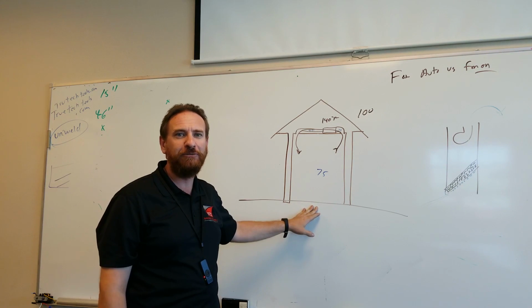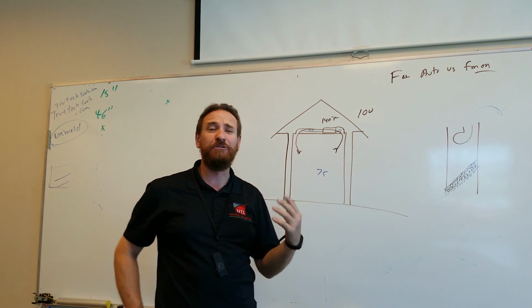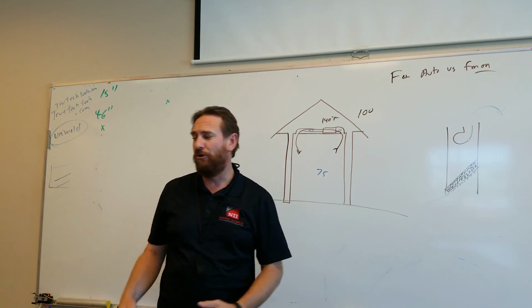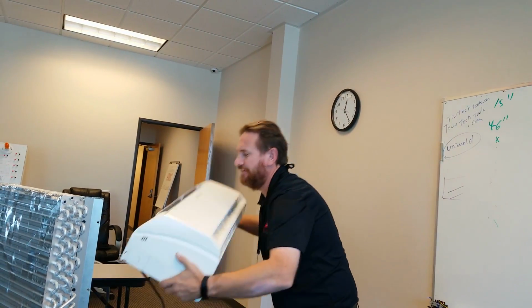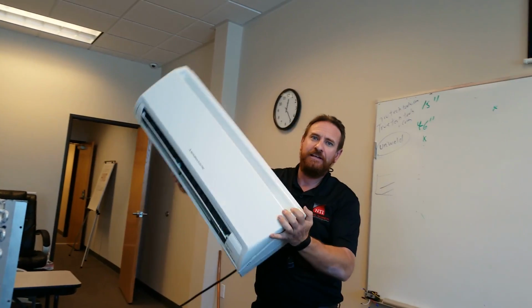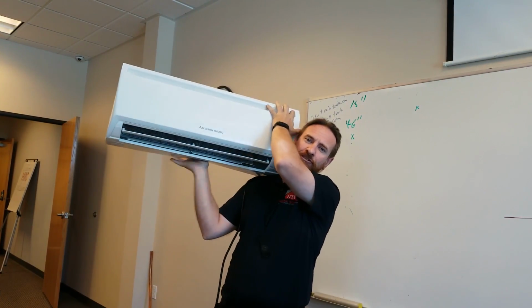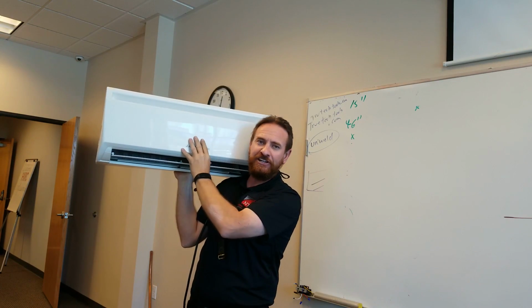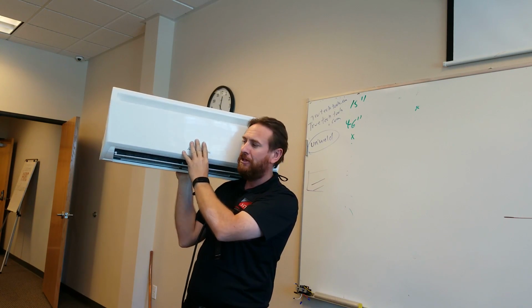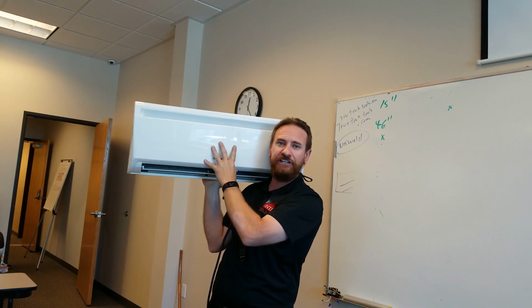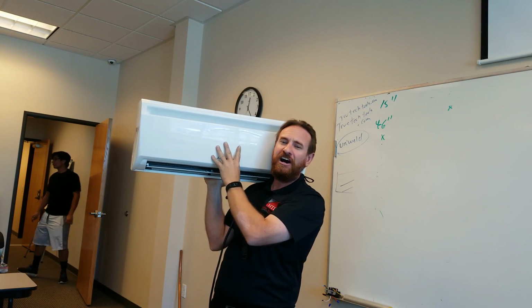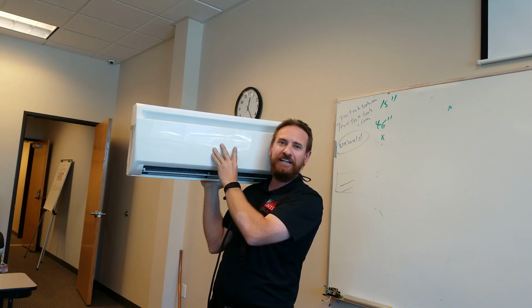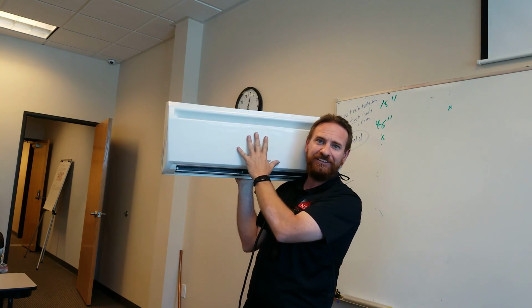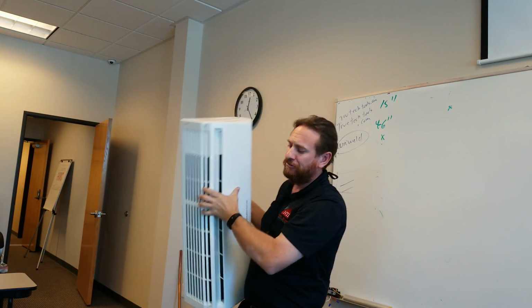unless you end up with the new variable refrigerant flow systems. And these systems are going to run non-stop, but not just a fan, the whole AC system. If you look over here, we have a ductless system. And a lot of these ductless systems now are using variable refrigerant flow technology. So it's not just that the fan's running all the time non-stop. The refrigerant that's running through the evaporator coil here is running at the same time. So we're constantly dehumidifying, constantly cooling the air, and there's no ductwork. So we don't have to worry about the attics getting hot at all. So there's an incredible energy efficiency in here.